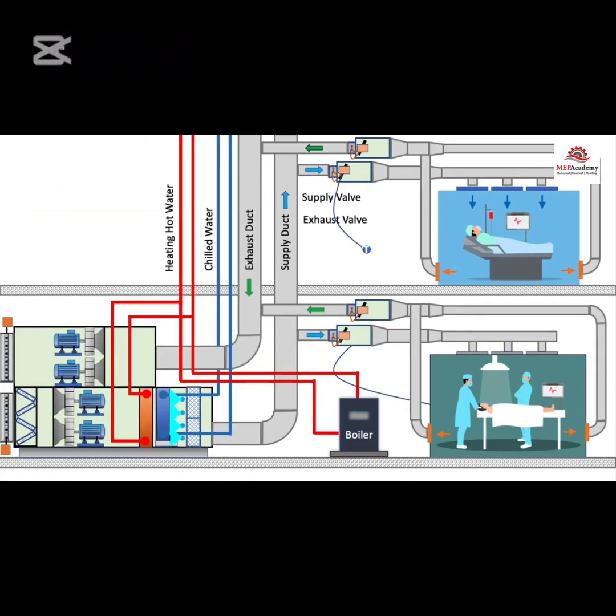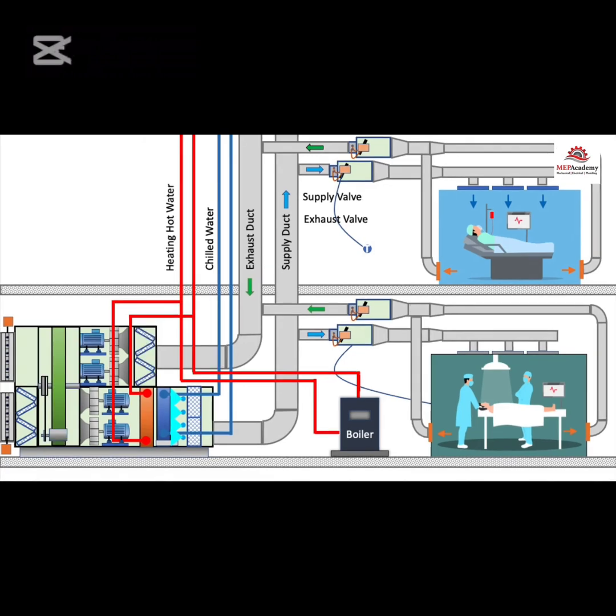Since this is an operating room, we'll add a UV (ultraviolet) lighting system to kill any bacterial, viral, or fungal organisms in the air and on or near the cooling coil, including the drain pan where water accumulates before draining. Next, we'll add an energy recovery wheel to save energy and capture the heat that is being wasted.